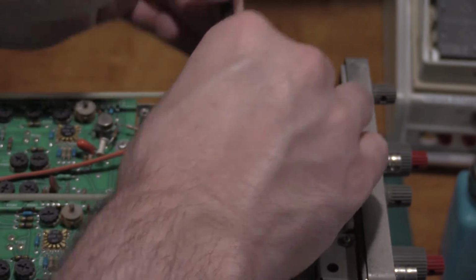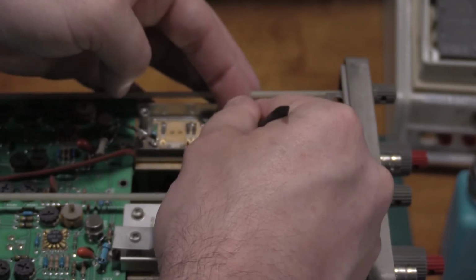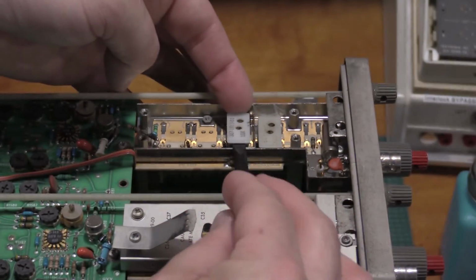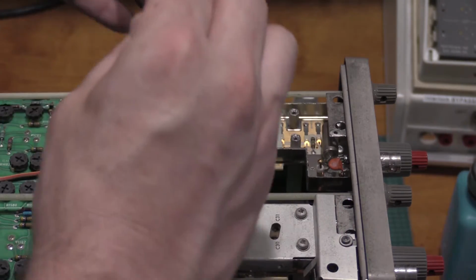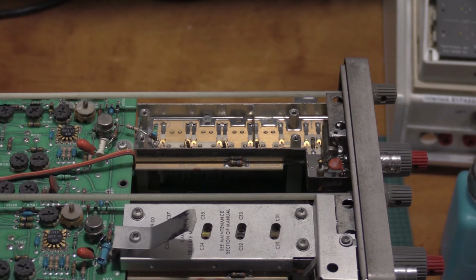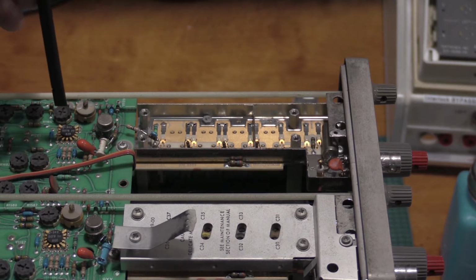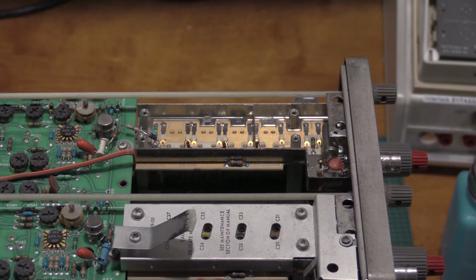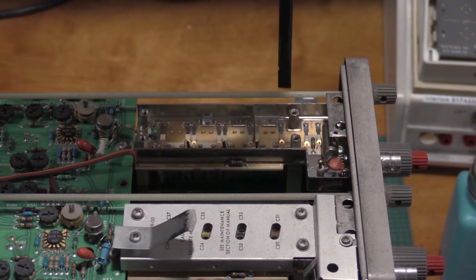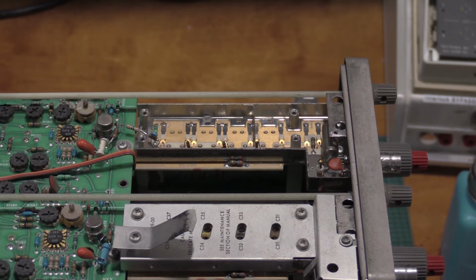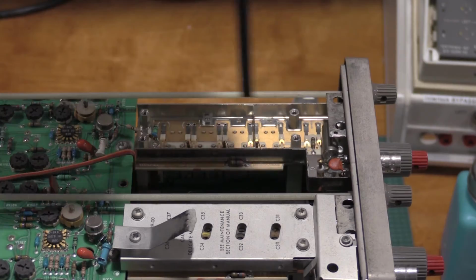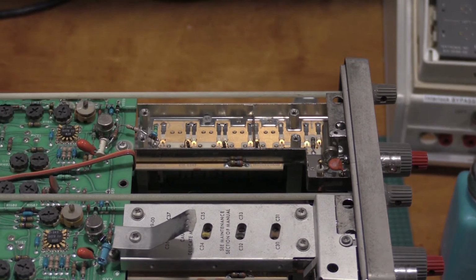Now it is very important that you maintain the order of these attenuators, because the indexing of the drum switch matches up with how the signal passes through the attenuators to get the proper attenuation. Because this is such a wideband amplifier, 100 megahertz, the gain is fixed. They don't adjust the gain of the amplifier. They attenuate the signal coming into the front end, so they have a set gain, which allows them to widen the bandwidth of the amplifier, and then the scale is how much signal goes into the front end.